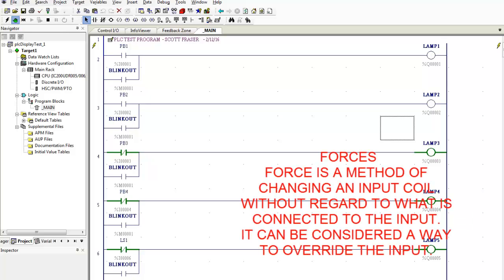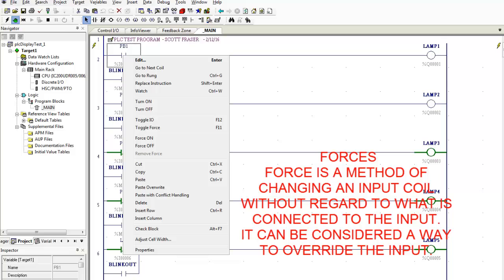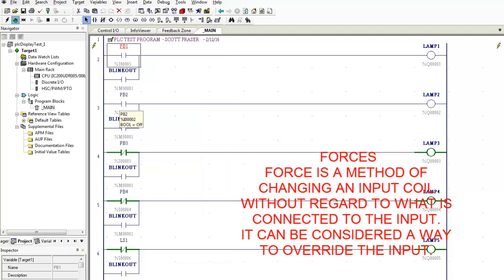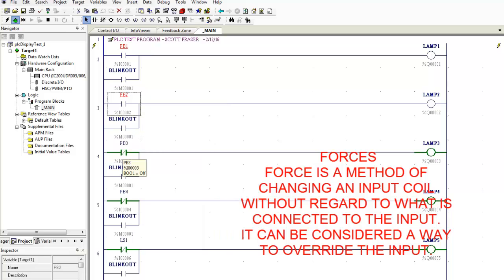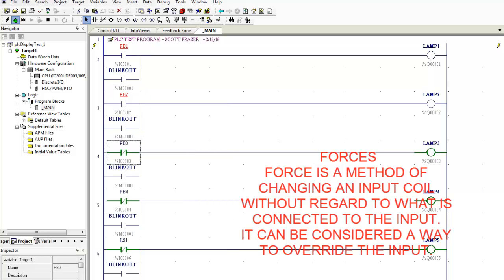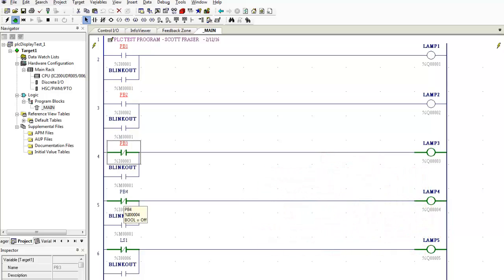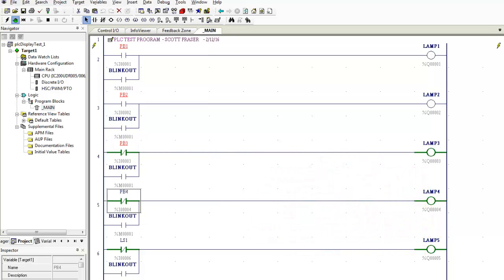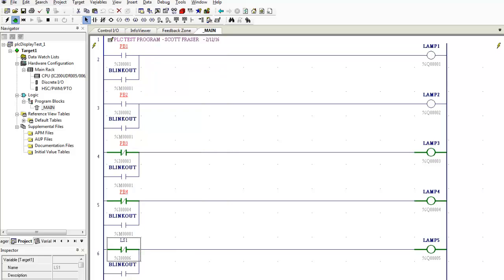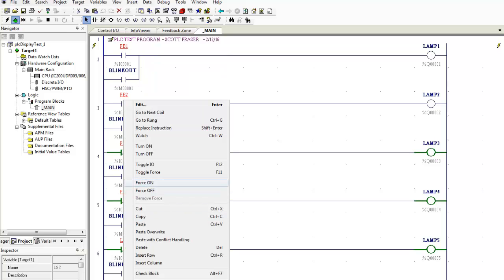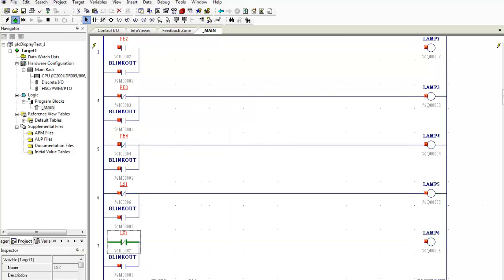So what I'm going to do is I'm going to use something called forces. I'm going to force these inputs on or off. So I'm going to come over here right click on that input and I'm going to force it off. I'm going to do this with all of my inputs. Force them all off. Selecting them one at a time. Forcing them off. And again I'm doing this because I do not have my input connected to this PLC.